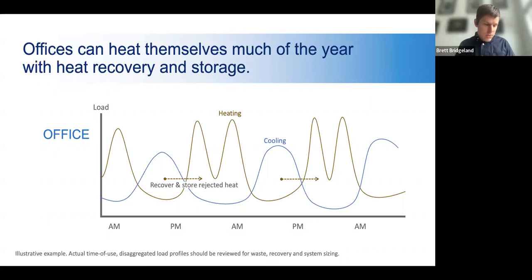That economizer cycle, or free cooling, has been touted recently, but in this new environment where we're trying to decarbonize heating, there's a new opportunity: rather than reject that unwanted heat from buildings, recover it, capture it, and store it until times of day when it's needed. Or, if there are opportunities to use it concurrently in different parts of the building—say, shifting heat from the core to the perimeter—we find offices can heat themselves for a big chunk of the year.